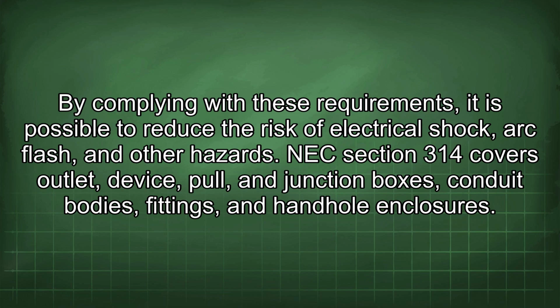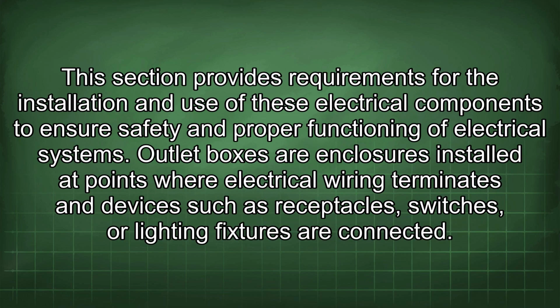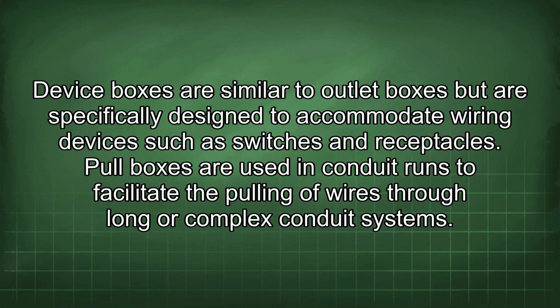NEC Section 314 covers outlet device, pull, and junction boxes, conduit bodies, fittings, and handhole enclosures. This section provides requirements for the installation and use of these electrical components to ensure safety and proper functioning of electrical systems. Outlet boxes are enclosures installed at points where electrical wiring terminates and devices such as receptacles, switches, or lighting fixtures are connected. Device boxes are similar to outlet boxes but are specifically designed to accommodate wiring devices such as switches and receptacles.